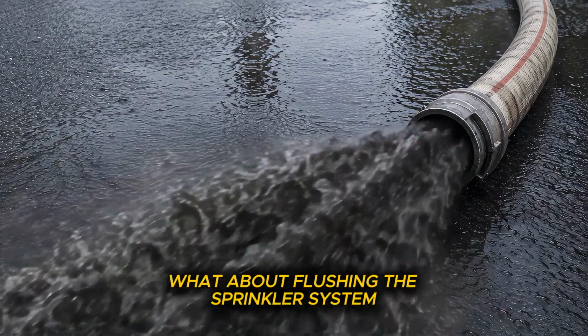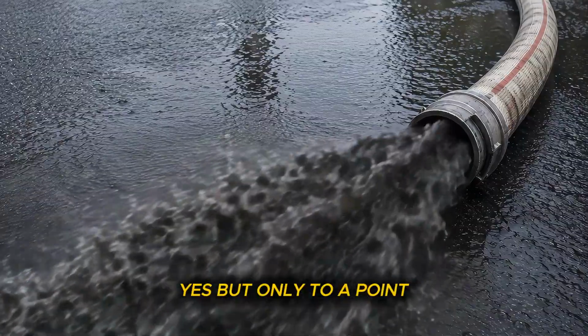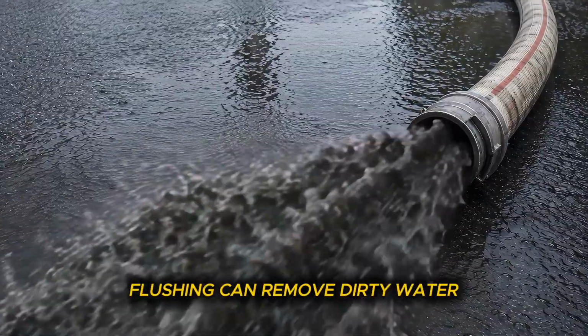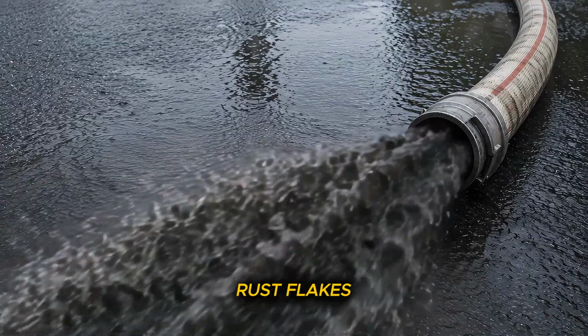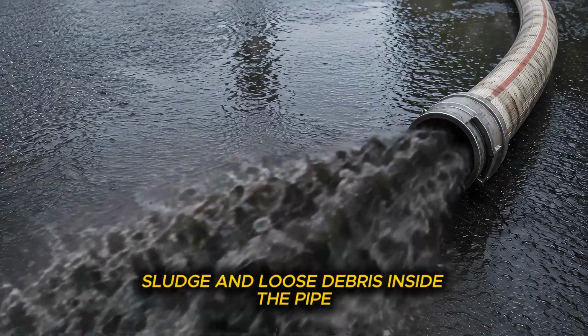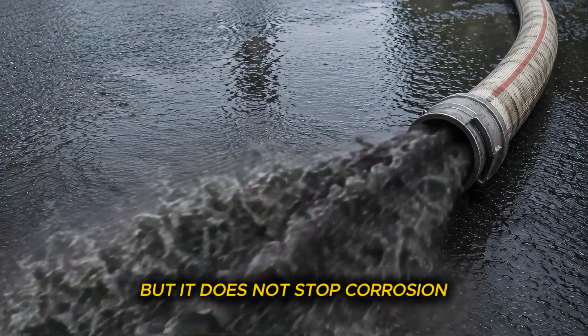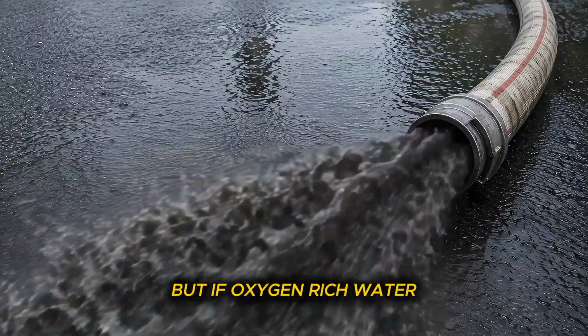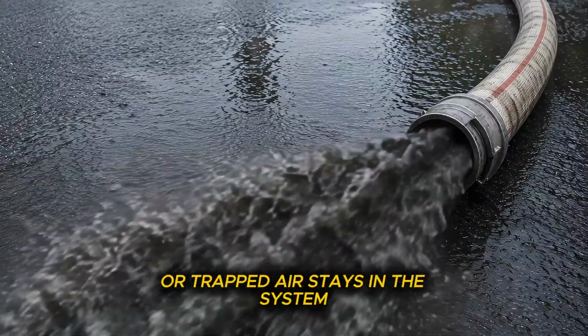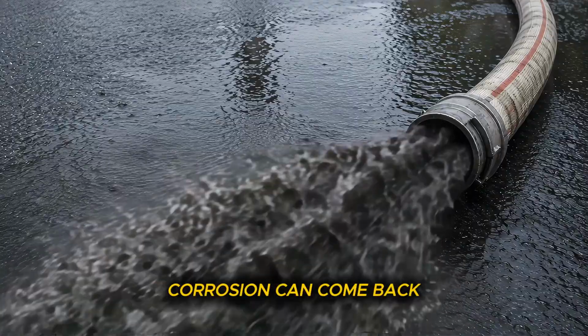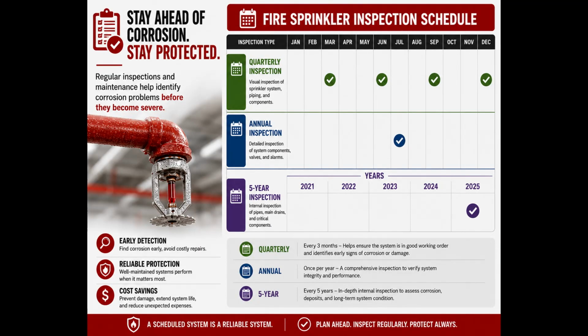What about flushing the sprinkler system? Does that help? Yes, but only to a point. Flushing can remove dirty water, rust flakes, sludge, and loose debris inside the pipe. But it does not stop corrosion. It cleans out some of the mess, but if oxygen-rich water or trapped air stays in the system, corrosion can come back. Regular inspections and maintenance help identify corrosion problems before they become severe.